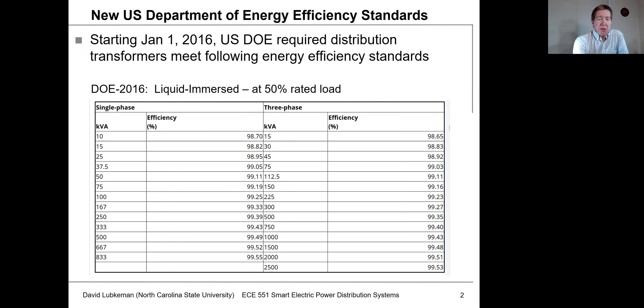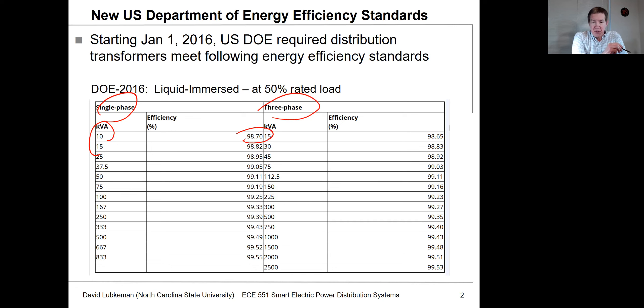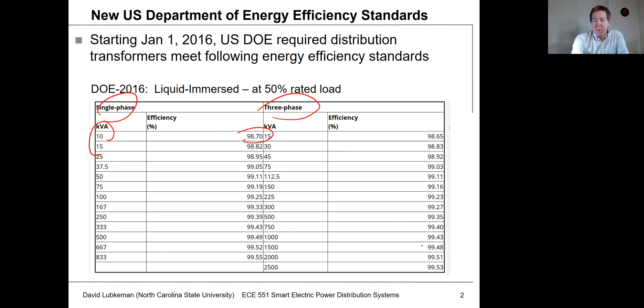In the table, they have a rating for each device, starting at 10 kVA for single-phase transformers and 15 kVA for three-phase transformers. When operating at 50% rated load, you need to have this minimum level of efficiency — whether that's no-load versus copper loss is up to the manufacturer. For the larger transformer sizes, we're operating up around 99.5%, and in some examples we're probably coming in around 98% or so.